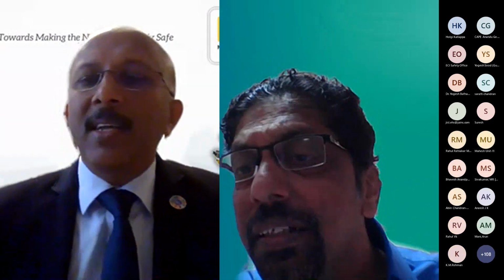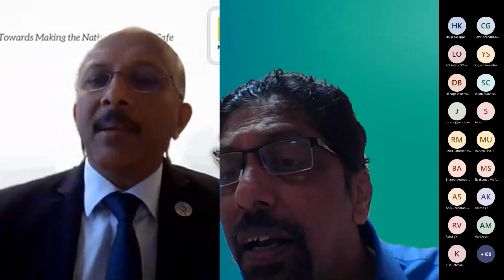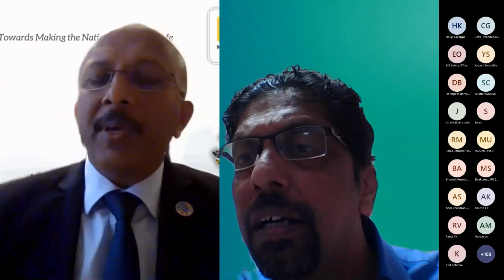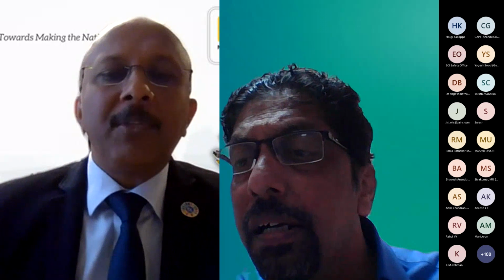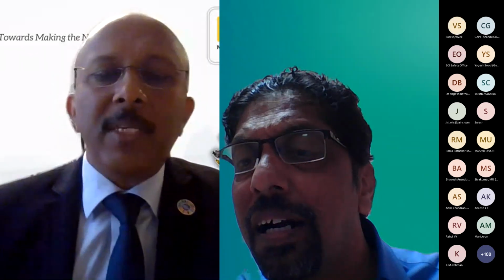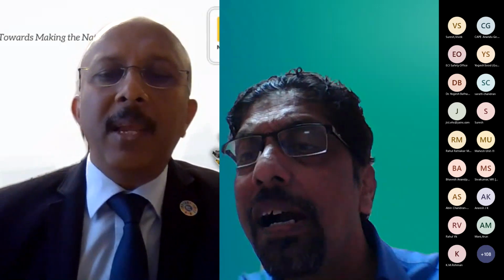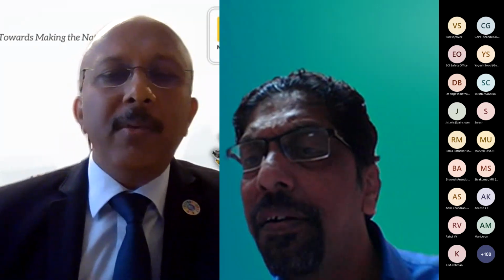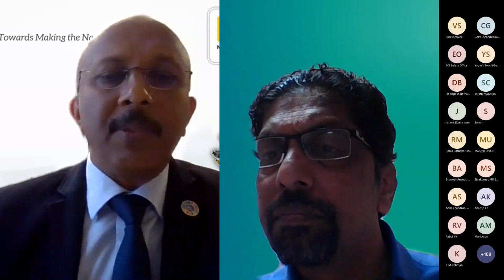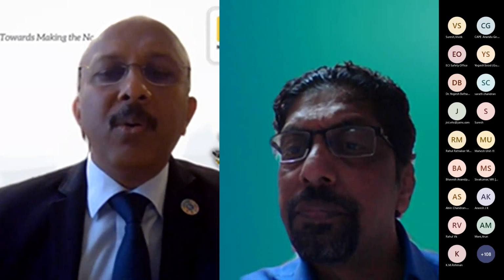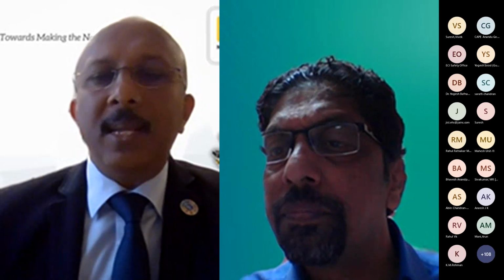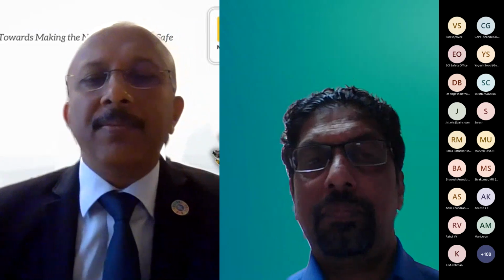Sambasiva Rao asked, is ESE, early streamer emission method, applicable in India for LPS? Simple answer is absolutely not. Even the existing regulation number 12, sub-regulation number 3 says every product used in electrical installation for the purpose of safety must conform to IS or IEC standards. ESE is not as per IS or IEC standards. As a result, it is not complying. Legally, it's not valid.